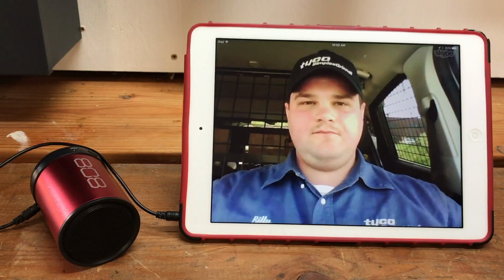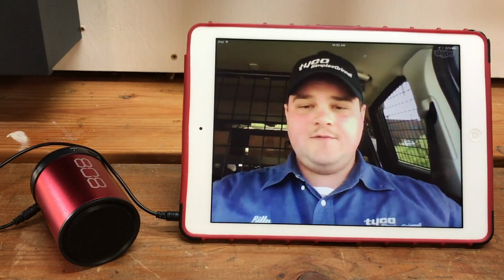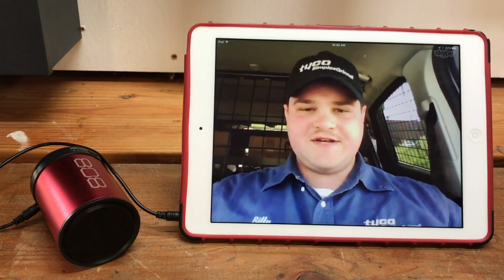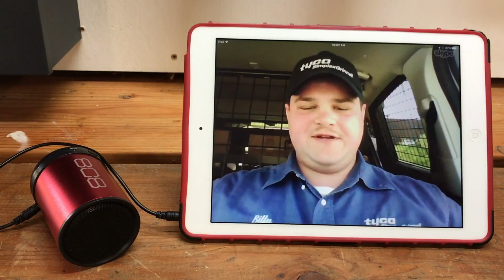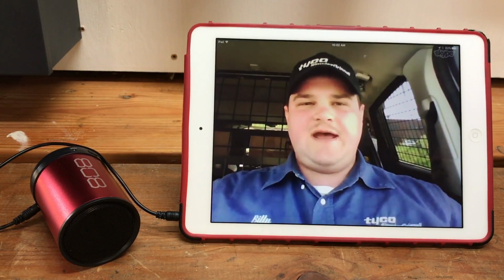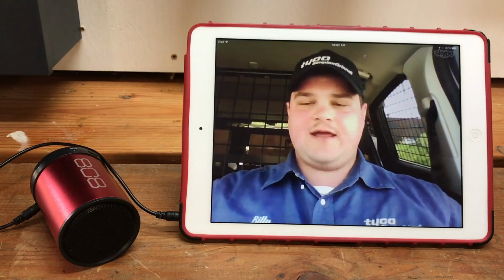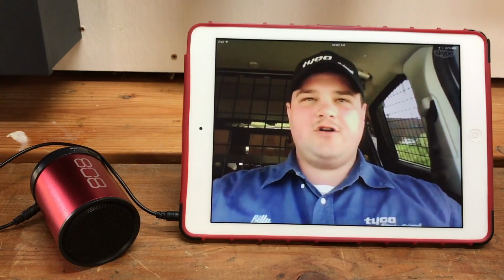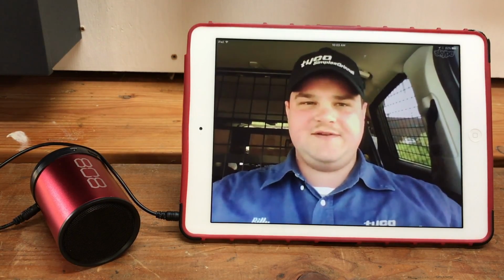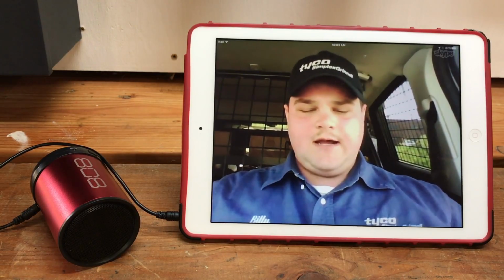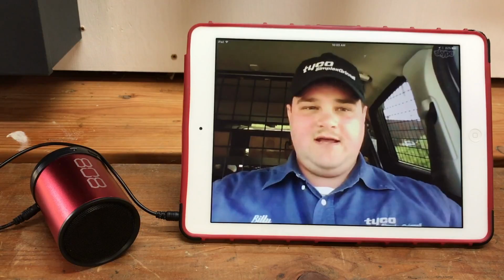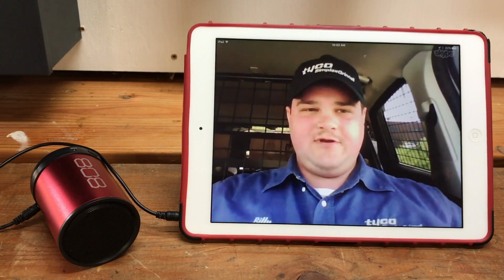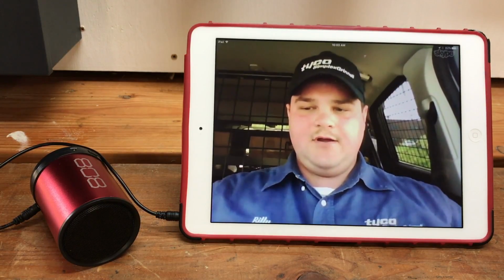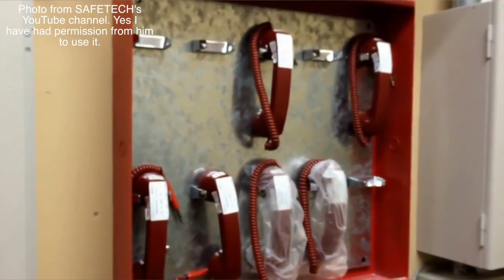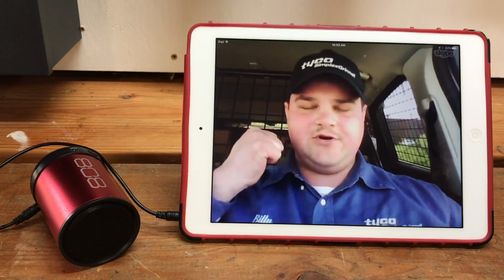What is a firefighter's telephone? A firefighter's telephone is what you'll run into mostly on larger systems. 4100s offer this option as a firefighter's accessory. What you have is Simplex offers phone receivers that actually plug into wall jacks that are basically on the walls, usually near stairwells at large apartment complexes, large multi-story high-rises, so that the fire department, when they enter the building during an actual emergency, they'll go to the panel or a set location to where all these receivers are held. We actually have cabinets that we install near panels that hold all these receivers. When I mention receiver, it's actually just like a regular telephone that you hold up to your ear.